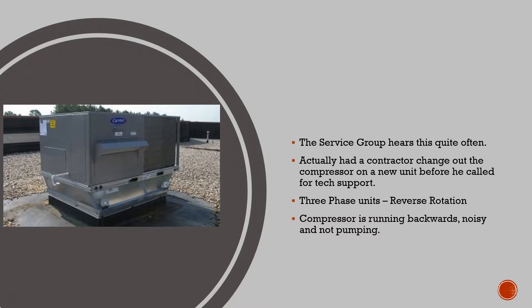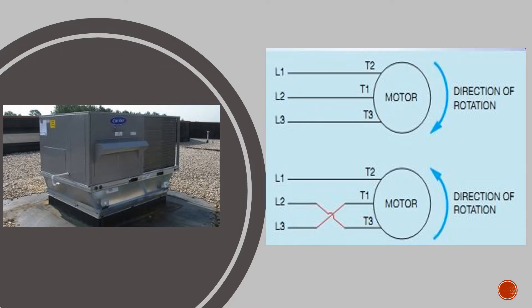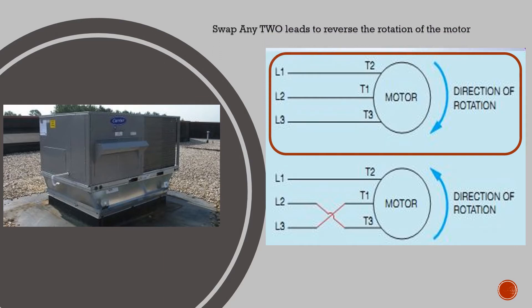In this example, we have a three-phase motor turning in the wrong direction. By swapping any two leads, we can reverse the rotation of the motor. By swapping L2 with L3, we change the direction of the motor.